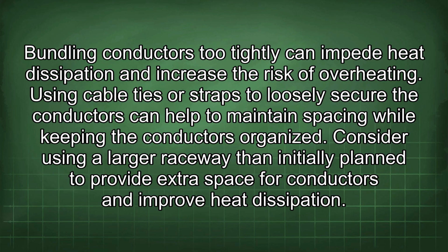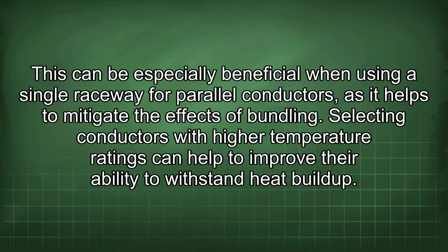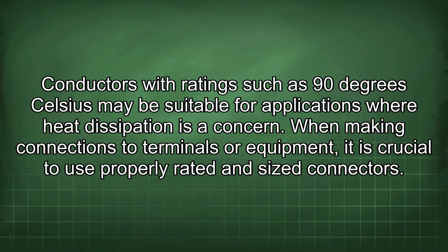Consider using a larger raceway than initially planned to provide extra space for conductors and improve heat dissipation. This can be especially beneficial when using a single raceway for parallel conductors, as it helps to mitigate the effects of bundling. Selecting conductors with higher temperature ratings can help to improve their ability to withstand heat buildup. Conductors with ratings such as 90 degrees Celsius may be suitable for applications where heat dissipation is a concern.